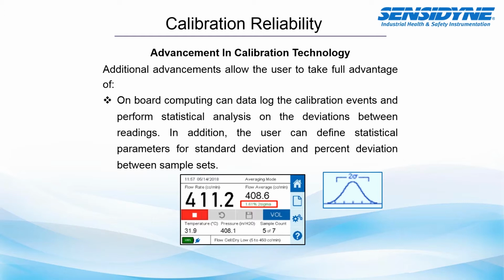So earlier we talked about precision. Well, how do I know that my readings are actually very close to one another? All right, on that targeting that we saw earlier, that we have a very close shot group. So one of the ways we can do that is we can look at the standard deviation or the percent deviation between each sample measurement. So some of the new calibrators on the market will actually show a 2 sigma standard deviation, and you can actually set this.